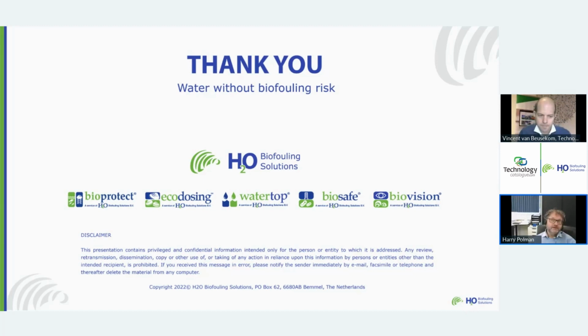Well, in principle, scale does not matter. Ecodosing works in small seawater intakes, small systems, but also very big systems. The picture I showed covered systems up to about 500 cubic meters per second, so very big seawater cooling systems. The technology works the same, because it's a matter of getting these pulses, these time intervals of chlorine or biocide, through the system efficiently.